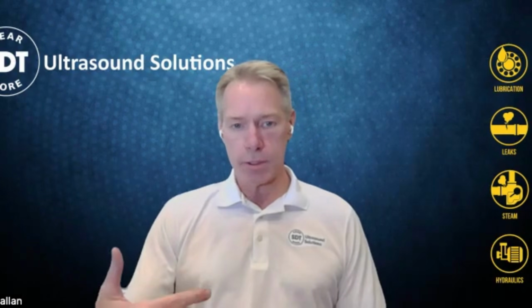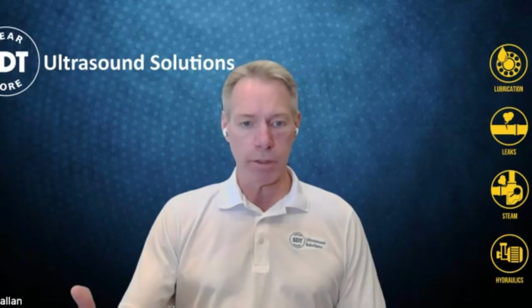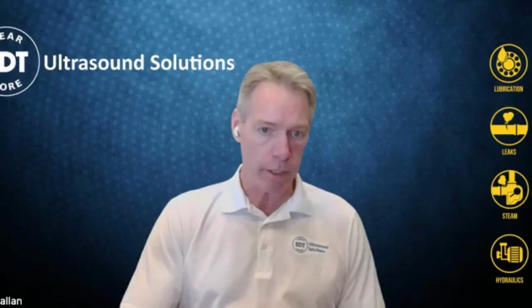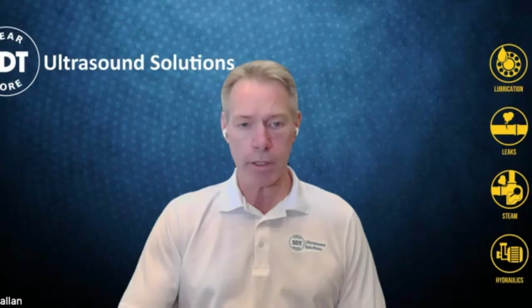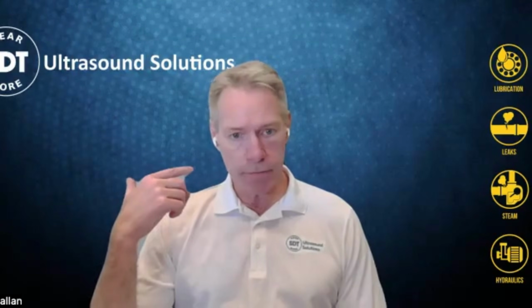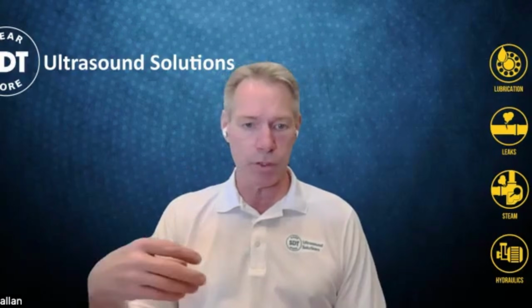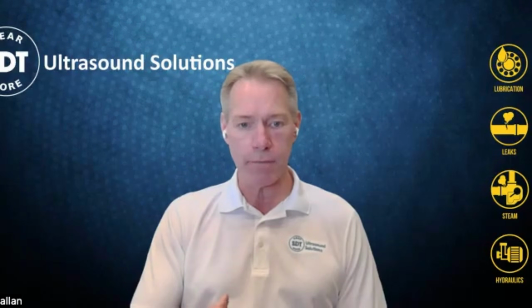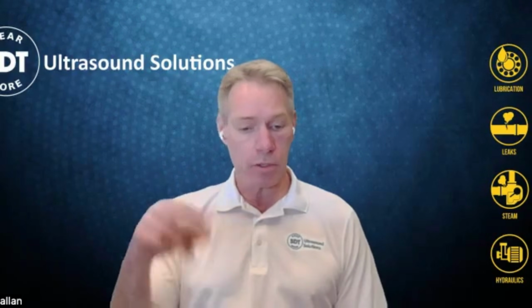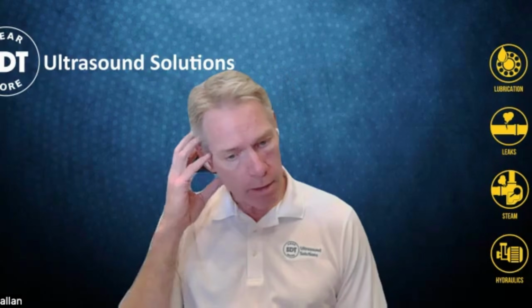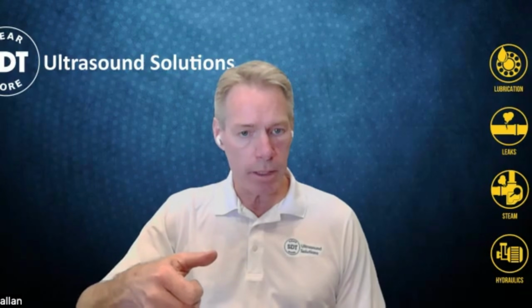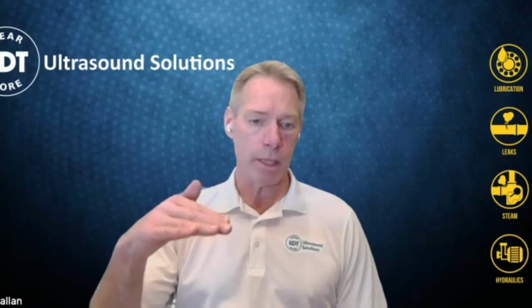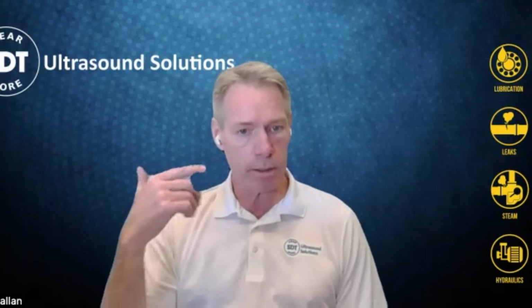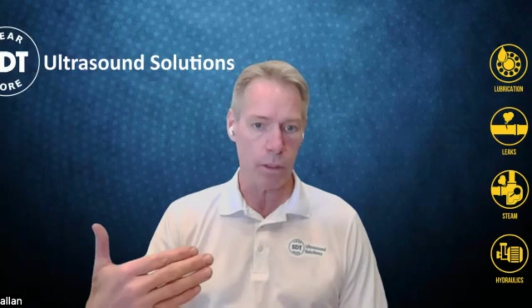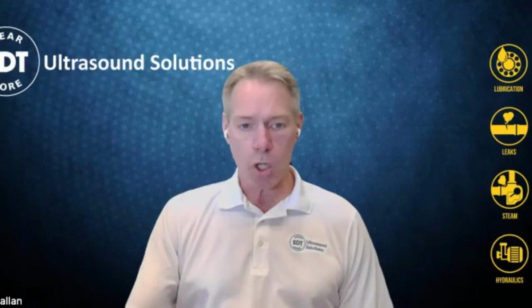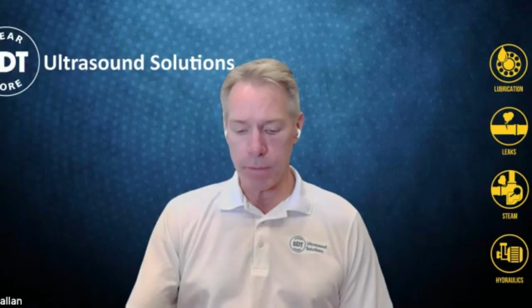Then you can get into digital decibel metering devices like our Lube Checker, for example. And our Lube Checker, it's a listen-only device, but it's not listen-only. It also gives you feedback. It gives you that decibel level. So as you're listening to the bearing, and as you inject grease into the bearing, you can see the decibel level drop, and you can hear the friction improve. So that's a quantitative re-greasing of the bearing.